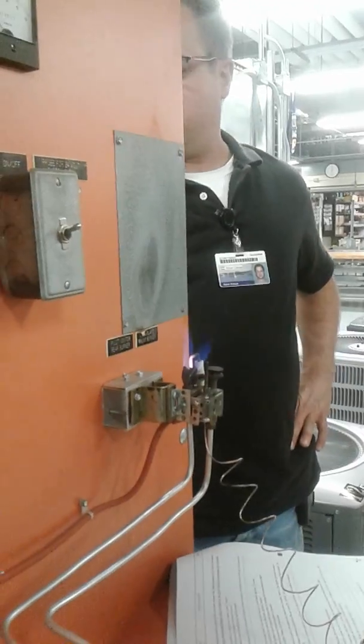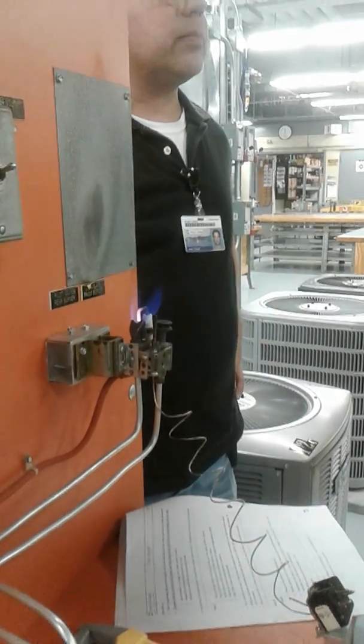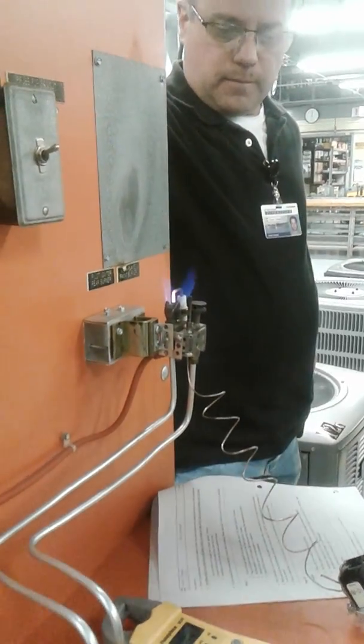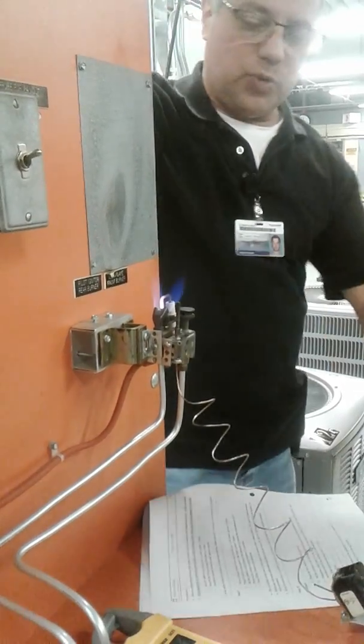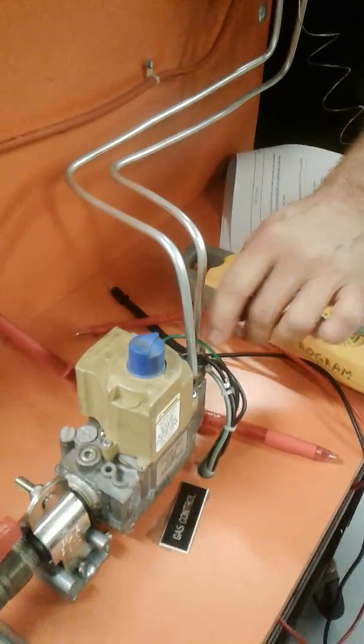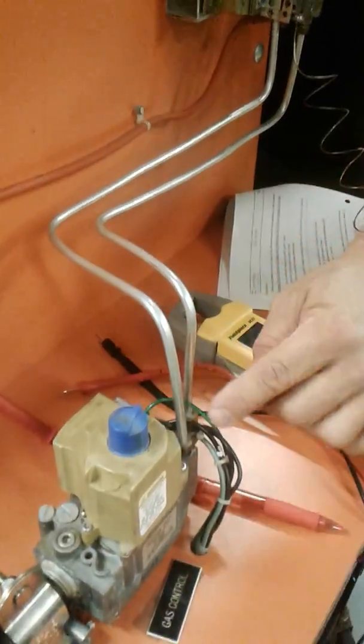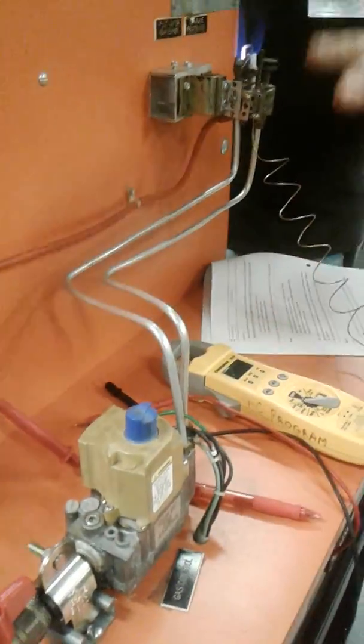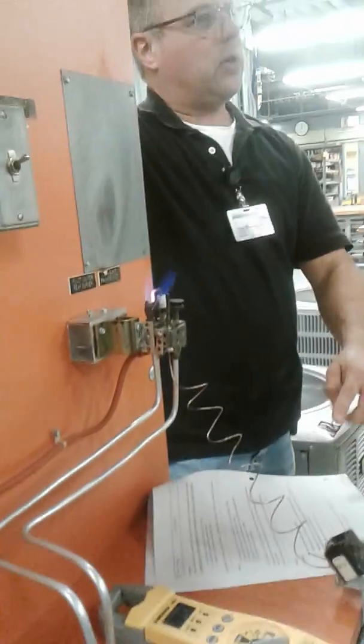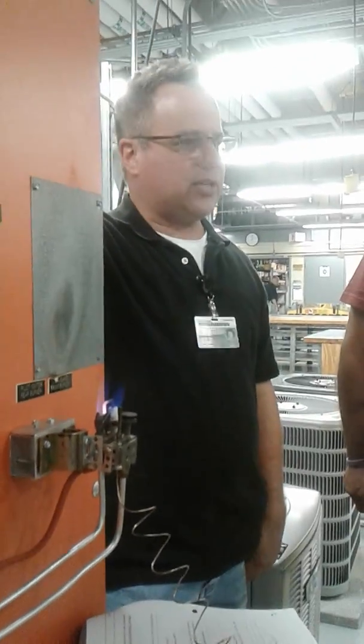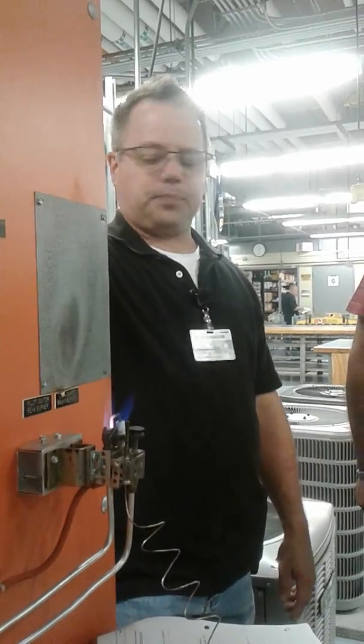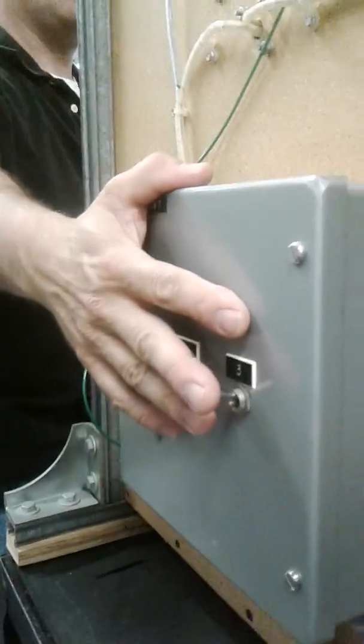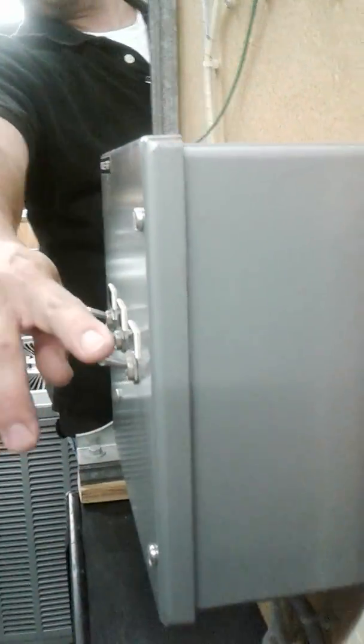Right? Okay. Very good. What if we were giving it power, but this wouldn't light up? Then our gas valve is bad, because the valve is probably bad inside or it's not opening. If we got 24 volts, I don't want to burn myself, we got 24 volts there, allowing the gas to flow, but it's not doing anything, the gas valve's bad. Okay. Now they're all on. Here's switch 3. Again.